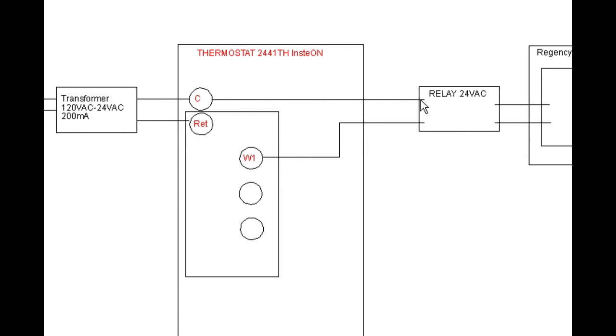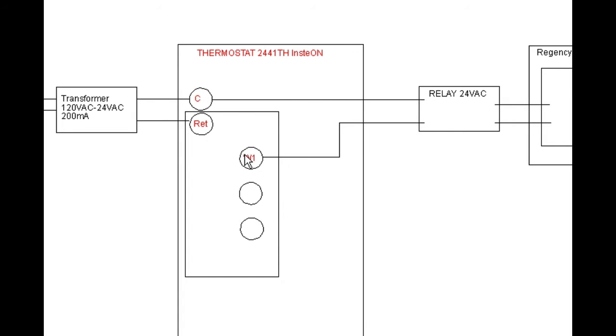It's always going to be applied at that point, and only at this point when it's called. So it comes from this side, stops here until heat is called, then it makes a line through here and pushes the other side of the 24 volts to this coil, which is on this part of the relay.